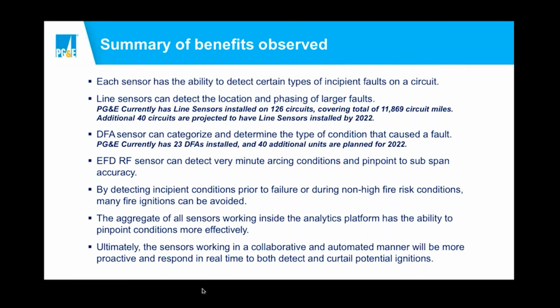Okay, thank you. All right, so just wanted to summarize some of the things we talked about - two key points. What we've found with all the work we're doing is that each sensor has its own areas of strength. Line sensors can detect large overcurrent faults, EFDs can detect arcing and sparking, and DFAs, our substation technologies, can tell what type of fault occurred, but not where. So individually, they do not provide a full picture. That takes me to my next point: ultimately all these sensors have to work together in a collaborative, automated fashion to come up with more proactive and real-time capabilities in detecting issues on our system.